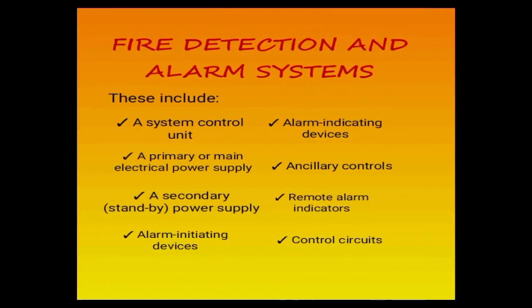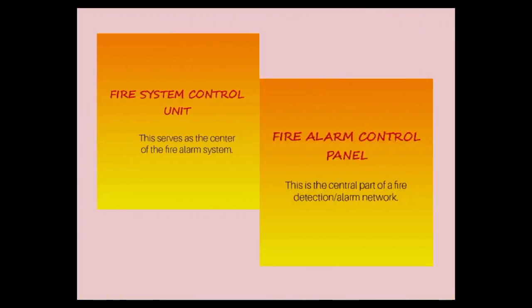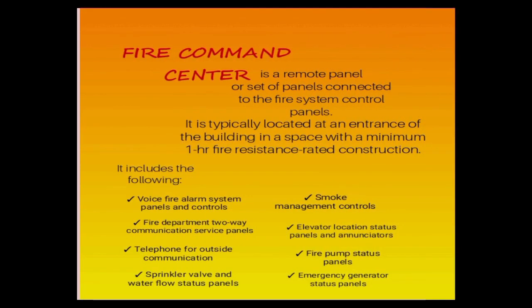Fire detection and alarm systems include a system control unit, a primary or main electrical power supply, a secondary standby power supply, alarm initiating devices, alarm indicating devices, ancillary controls, remote alarm indicators, and control circuits. Fire System Control Unit. This serves as the center of the fire alarm systems, while the Fire Alarm Control Panel is the central part of a fire detection or alarm network. Fire Command Center is a remote panel or set of panels connected to the fire system control panels.